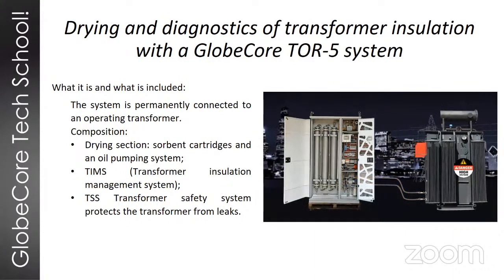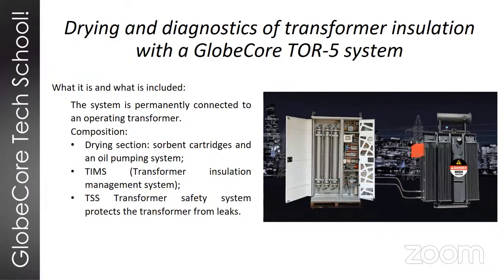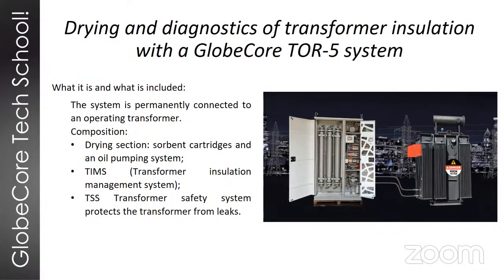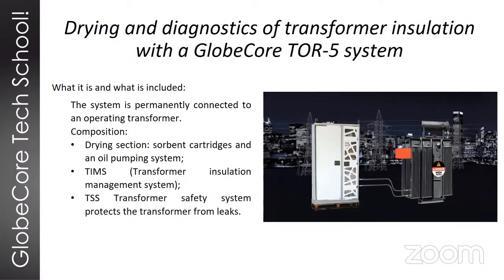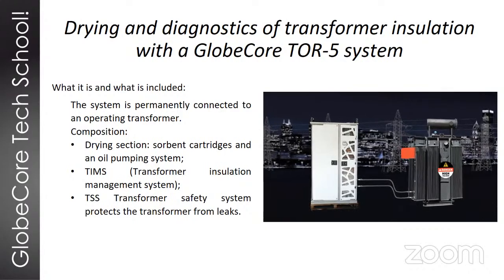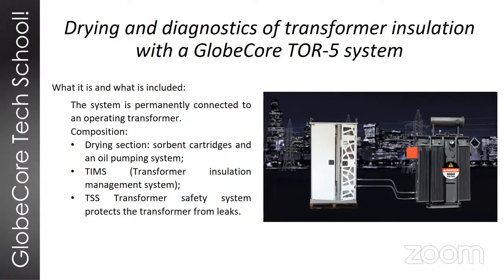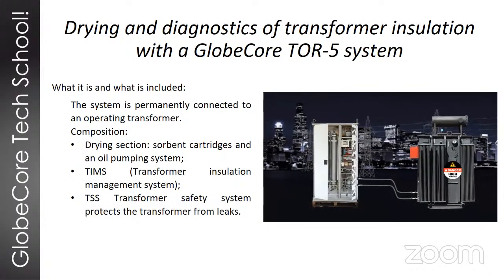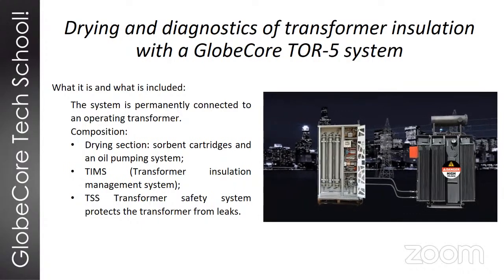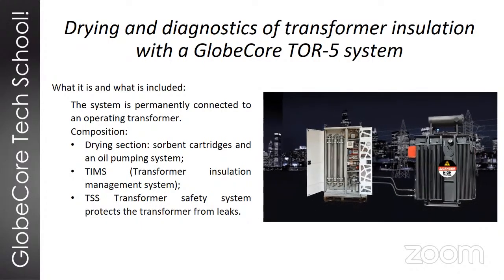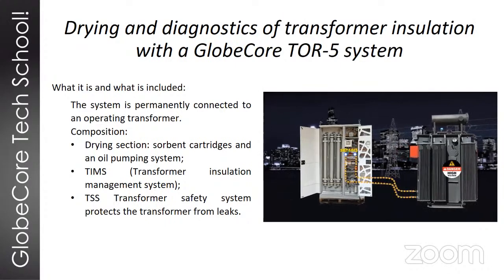The next component is the TSS system, a transformer safety system, and that is designed to be connected to the transformer tank and to protect the transformer first by removing any air from the hoses and pipelines, and also to control the level of oil in the transformer during processing. So, for example, if there is a leak, the system is automatically shut down and all the valves are closed to protect the transformer against such leaks.